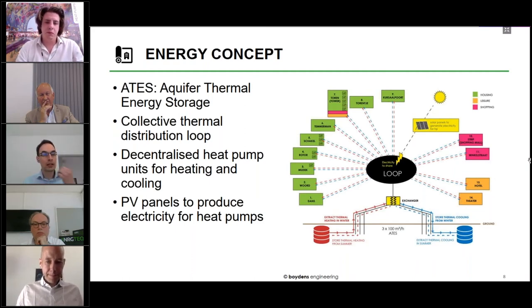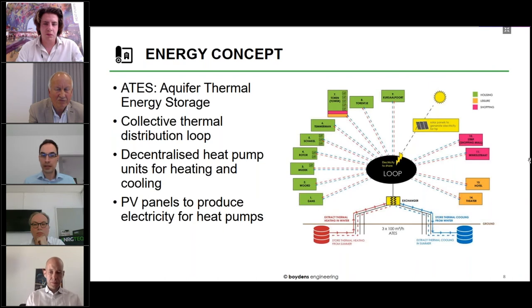So the energy concept is based on four main pillars. The main one, the first one, is the aquifer thermal energy storage system. Then there is a collective thermal distribution loop that connects the aquifer thermal energy storage with the decentralised heat pump units for heating and cooling that are locally producing the heat. And on top of that, there are still the PV panels that are there to produce electricity to compensate for the electricity used by the heat pumps.